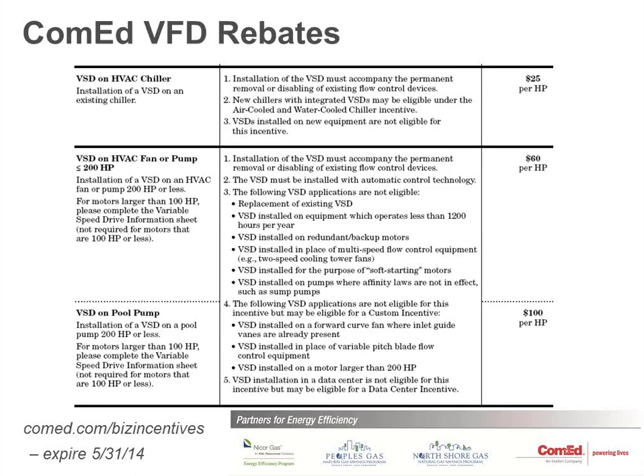If you put a VFD on a compressor, a chiller compressor, it's $25 per horsepower. The energy savings is not quite as great as the fan or pump savings would be. And if you want to do it on something else, you can do it as a custom rebate.